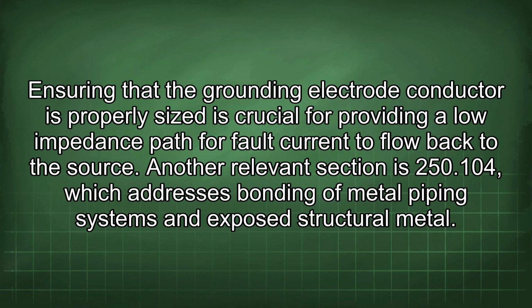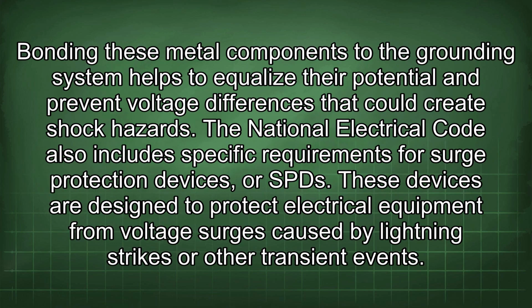Another relevant section is 250.104, which addresses bonding of metal piping systems and exposed structural metal. Bonding these metal components to the grounding system helps to equalize their potential and prevent voltage differences that could create shock hazards. The National Electrical Code also includes specific requirements for surge protection devices, or SPDs.